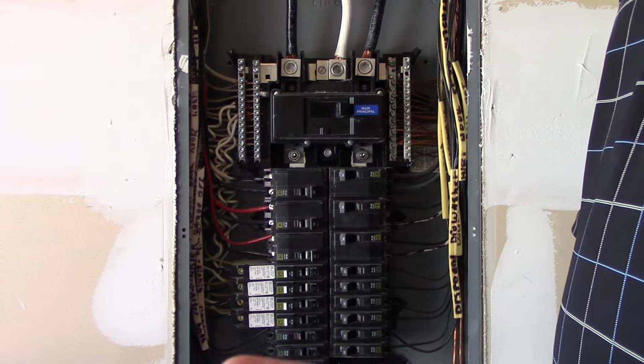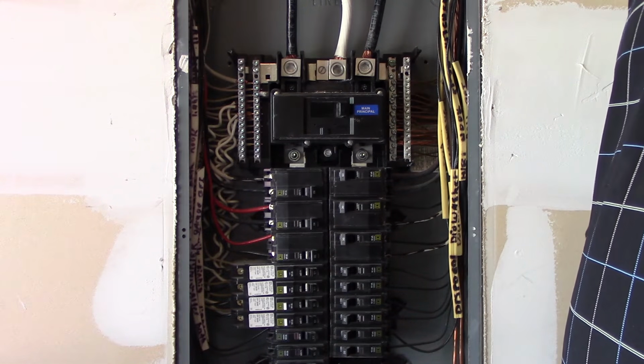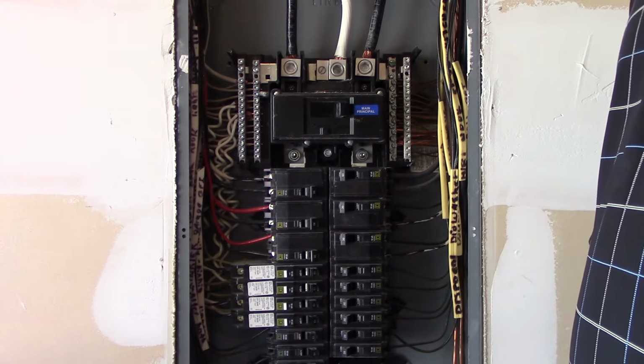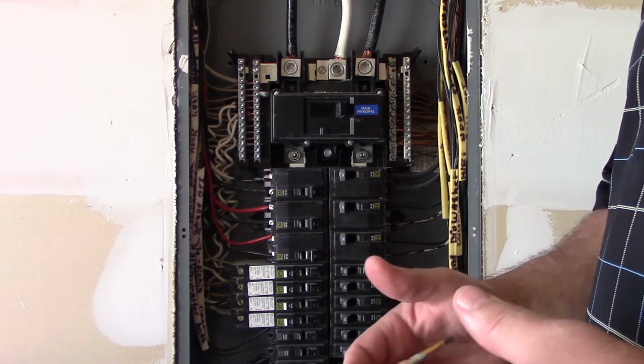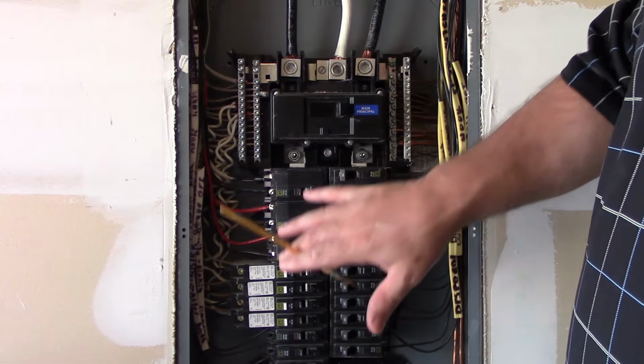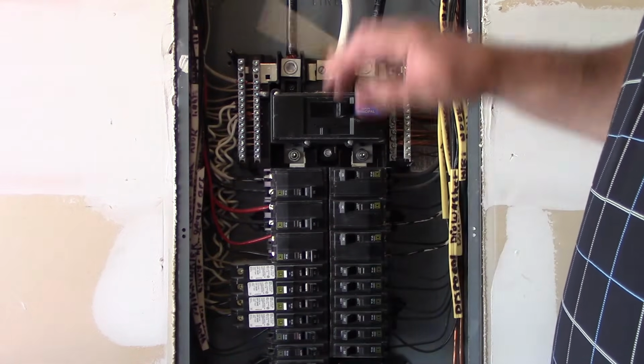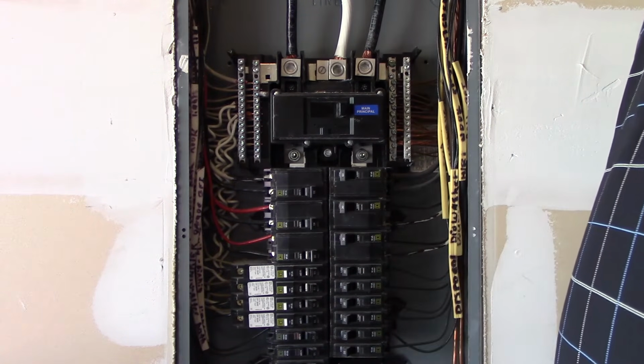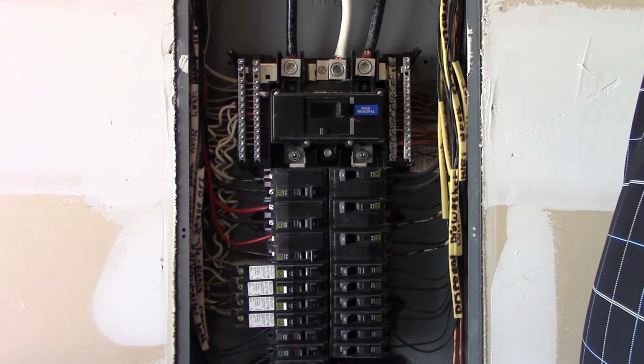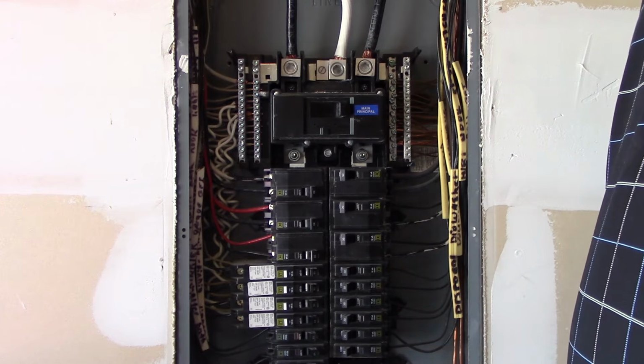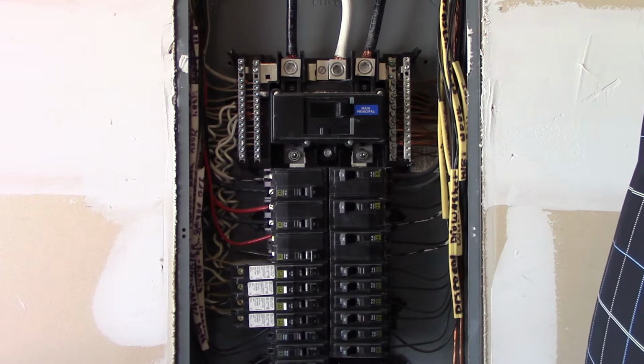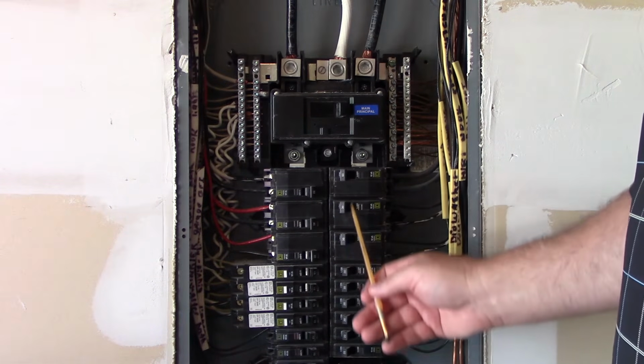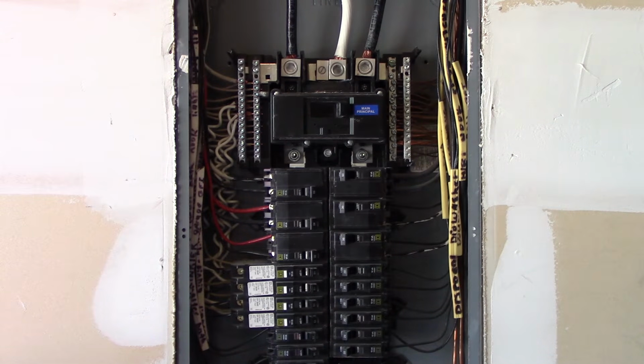Okay, and I get Cutler Hammer and a couple of the others, Thomas & Betts. All of those create what's called classified breakers, which have been evaluated for use in a specific manufacturer's enclosure and on their panel board and in their cabinet. So that's what you utilize that. And there's a list out there that you can get. In fact, we'll post it up on Master the NEC for you to be able to download if you'd like it. All right, so we've looked in here, and all of these happen to be all Square D, so everything looks good here.